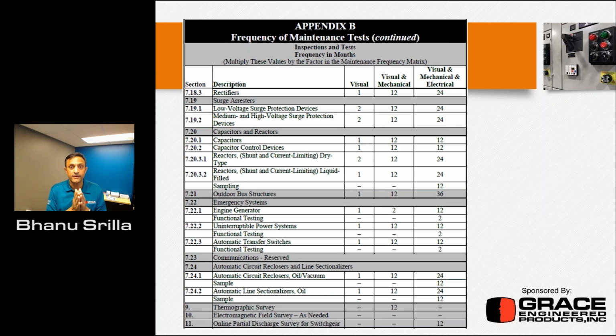And the PPE rules apply per your facility guidelines. So if your facility requires an arc flash category or category 4 40 cal PPE to be worn when you are entering the electrical room, you need to follow that, because that's not defined by me or OSHA. That's your facility's procedures. However, if your procedure calls for arc rated, you can use that too, because what is normal is a very subjective term, right? So from an electrical standpoint, work performed in an energized fashion when the doors are open is not normal operation. That's energized work, so you need to don the PPE appropriate for that arc flash category, okay? And if the work is being performed outside the cabinet, and you meet all 6 conditions of NFPA 70E, then it is normal operation. And whatever is defined as normal operation PPE by your facility, you need to follow that, okay? Hope that answers the question.